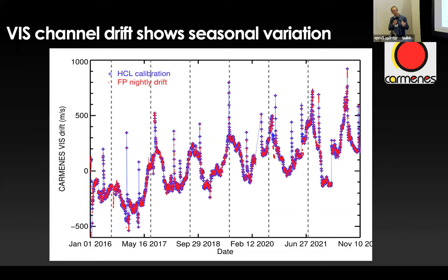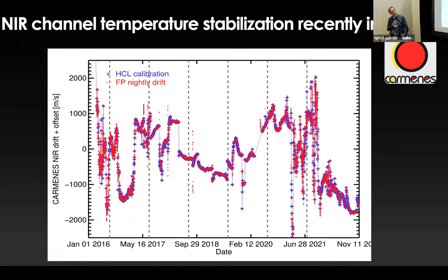So just before you run away, this was sort of new, and the system for the temperature calibration was something that was not that well tested, I guess, at that point. You can see a lot of chaos in the beginning, and you see it smoothing down in 2018 to 2020. Then chaos happened, and we have now really implemented a new temperature calibration system, a new control for the nitrogen supply, and that is supposed to deliver much better precision now. So this is something that you want to calibrate out, and of course you can imagine that there's a limit to it, right? So this is just to show you what we deal with, and that is essentially it.